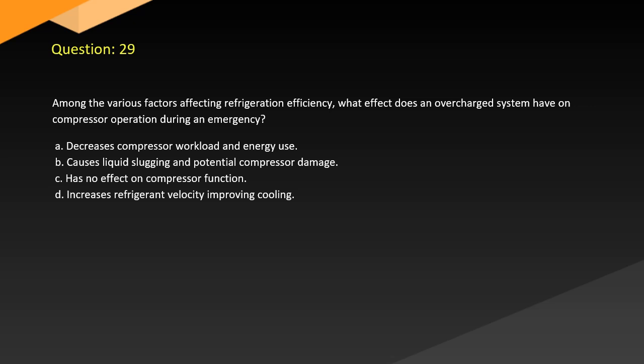Question 29. Among the various factors affecting refrigeration efficiency, what effect does an overcharged system have on compressor operation during an emergency? A. Decreases compressor workload and energy use. B. Causes liquid slugging and potential compressor damage. C. Has no effect on compressor function. D. Increases refrigerant velocity, improving cooling.